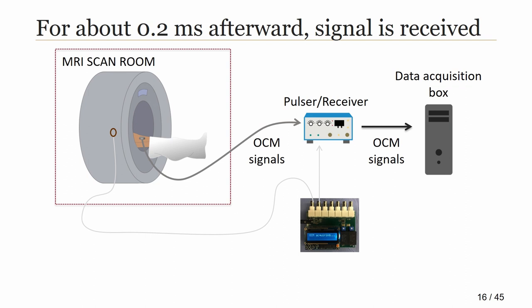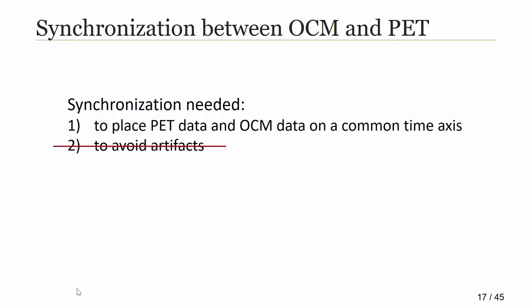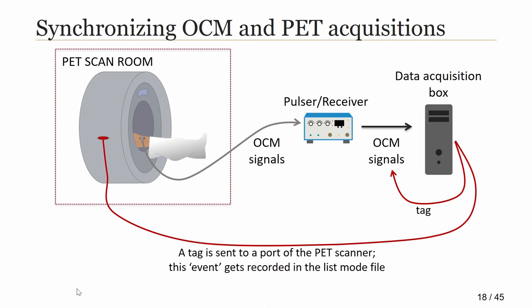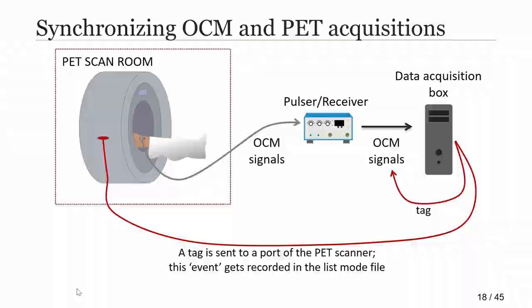In one application we use OCM sensors with PET instead of MRI. Synchronizing PET and OCM acquisition is actually easier, because there's no artifact issue — firing the sensor during data acquisition does not create artifacts in PET. The goal of synchronization in this case is simply to put PET and OCM data on the same time axis. This is done by having the data acquisition system stamp markers simultaneously on both the OCM data stream and the PET data stream, recorded as events in the raw PET data file, called the listmode.